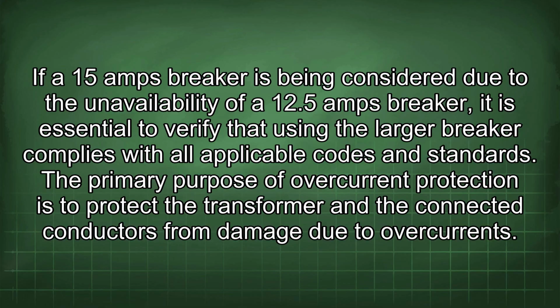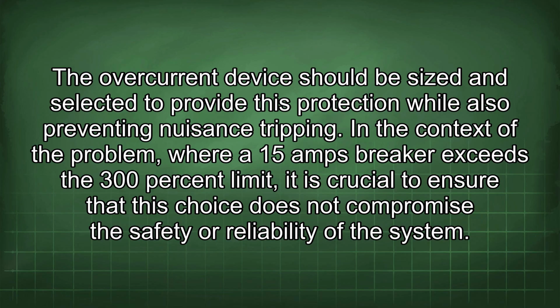The primary purpose of overcurrent protection is to protect the transformer and the connected conductors from damage due to overcurrents. The overcurrent device should be sized and selected to provide this protection while also preventing nuisance tripping. In the context of the problem, where a 15 amps breaker exceeds the 300% limit, it is crucial to ensure that this choice does not compromise the safety or reliability of the system.